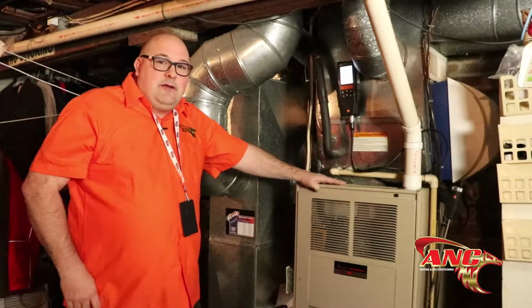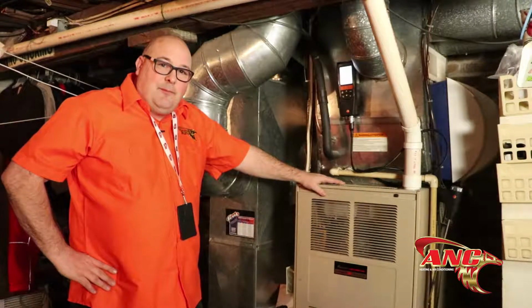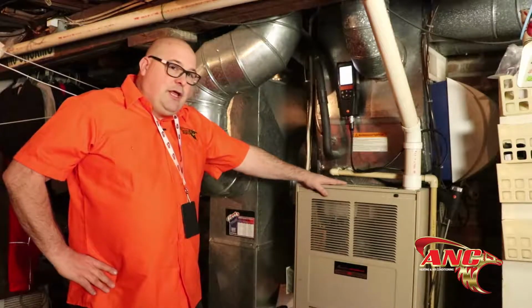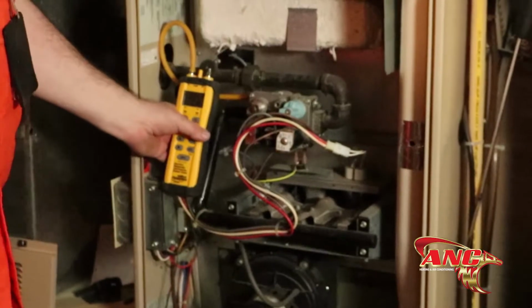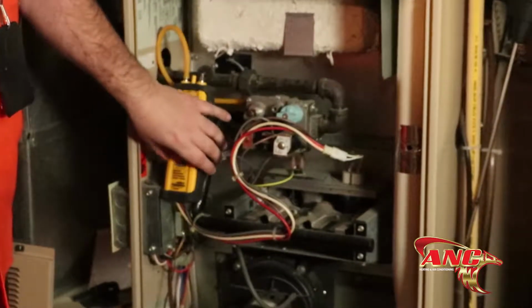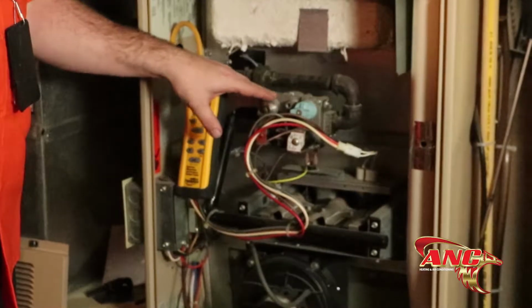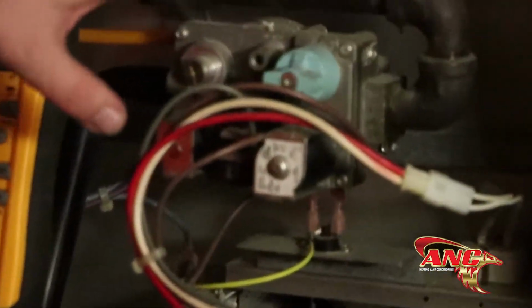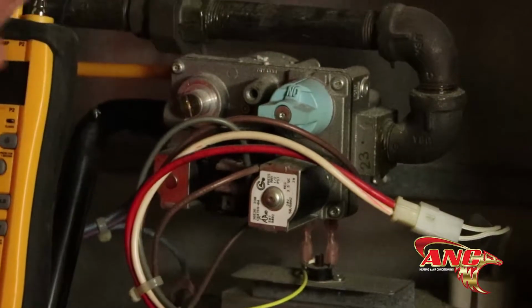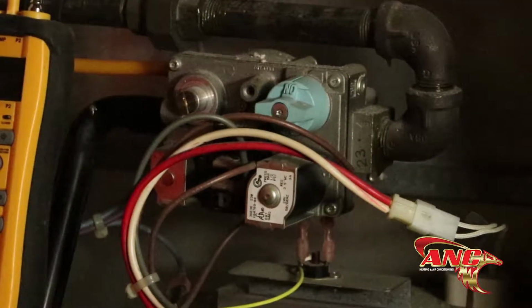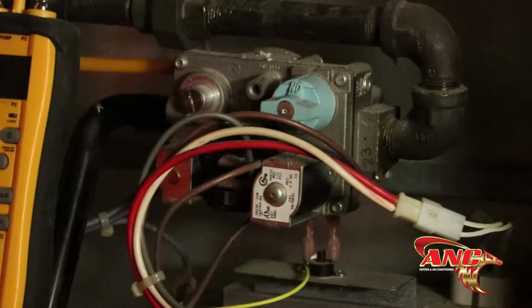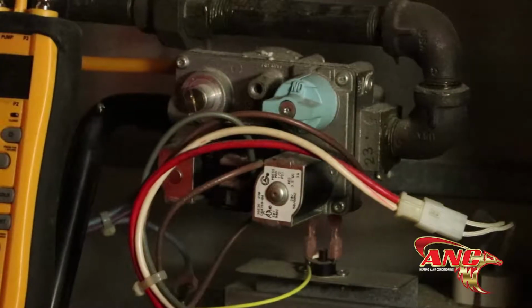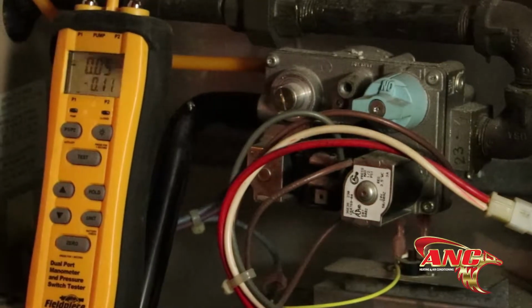In the past, it's always been guy goes down into the basement, not really sure what he does. You probably hear him banging around a little bit down there. We're going to encourage you to come on down and check out and see what we do. So let's take this apart, and who knows what we're going to find. We're going to check for the gas pressure, and if they're not checking your gas pressure, they're doing you a huge disservice. This is a single stage, but on a typical two-stage furnace, you're going to have two gas pressure readings. And if those gas pressures aren't right, it could A, cause damage to your furnace, and B, you're not getting the efficiency that you paid for when you bought the system.